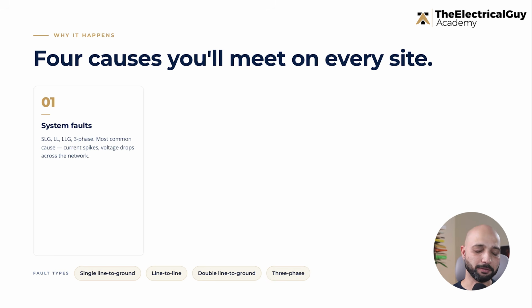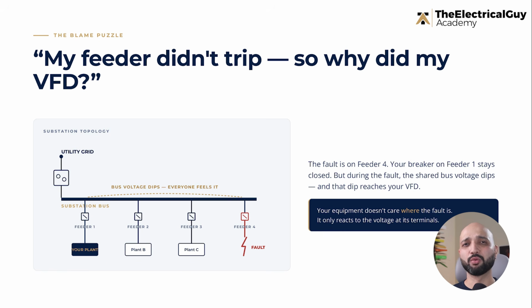Now here is an important point. A voltage sag can happen even when the fault is not on your own feeder. Suppose your plant is connected to feeder number 1 from a substation. A fault happens on feeder number 4 from the same substation. Your feeder is healthy, but during the fault, the substation bus voltage may dip. So your plant will also see a voltage sag. In this case, your supply may not get interrupted because your feeder breaker has not tripped, but your equipment may still trip because of the voltage sag.